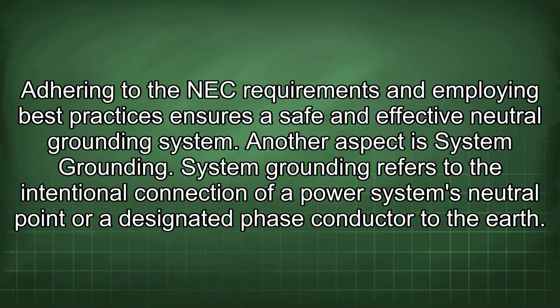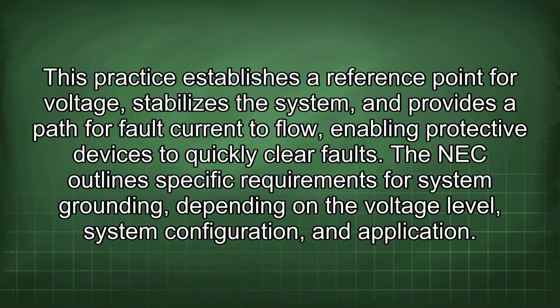Another aspect is system grounding. System grounding refers to the intentional connection of a power system's neutral point or a designated phase conductor to the earth. This practice establishes a reference point for voltage, stabilizes the system, and provides a path for fault current to flow, enabling protective devices to quickly clear faults. The NEC outlines specific requirements for system grounding depending on the voltage level, system configuration, and application.